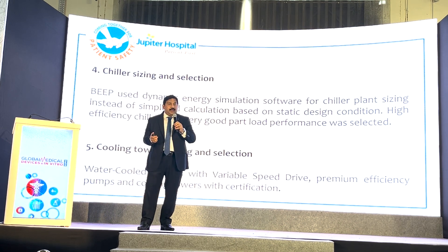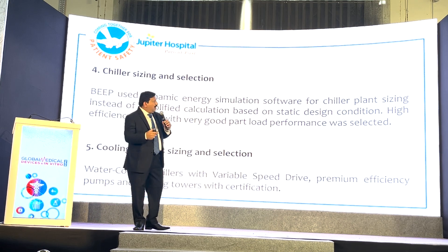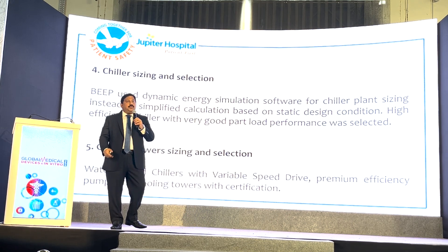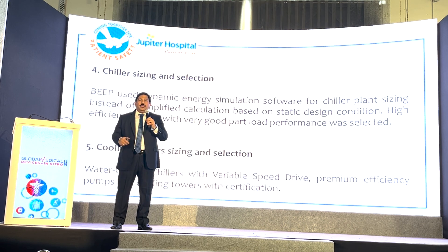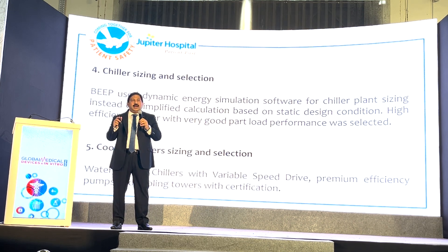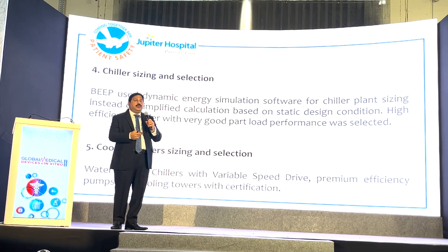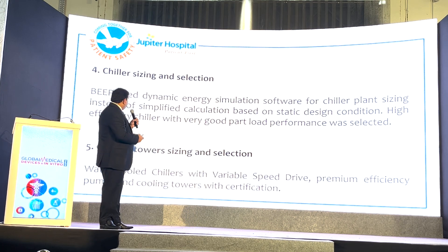Can you have 300 into 3? Yes. You can start with 300 into 2 numbers and later add one more when required. But all these things — chiller efficiency plays an important role. There is no point going for higher tonnage and then using VFDs; that is not going to solve the problem. We need a very clear idea of what your diversification is and what chiller you need — that is going to make a huge impact from an energy saving point of view.